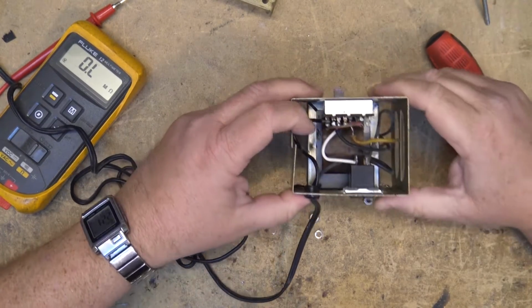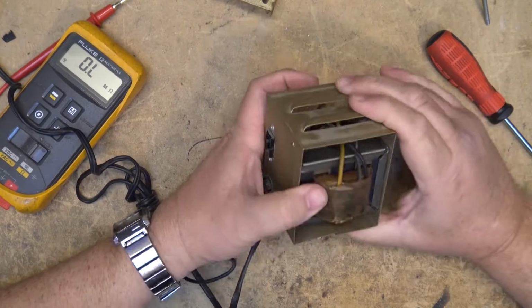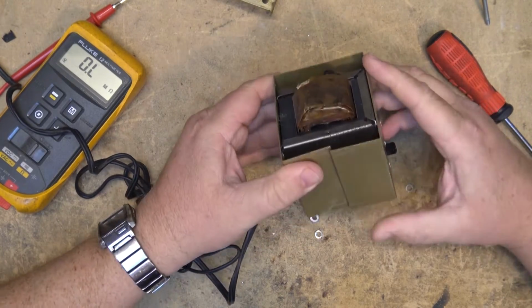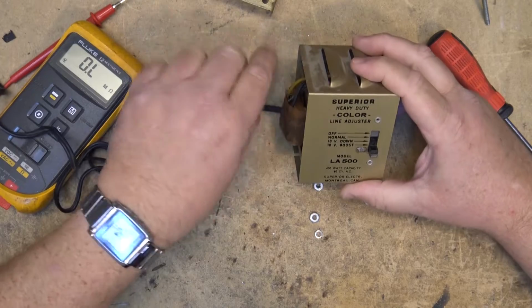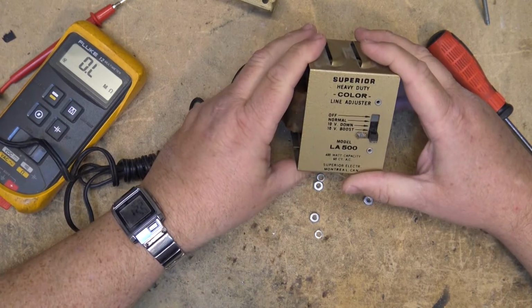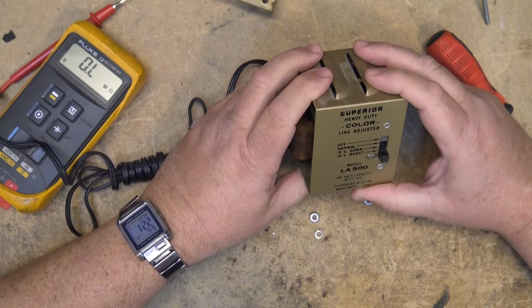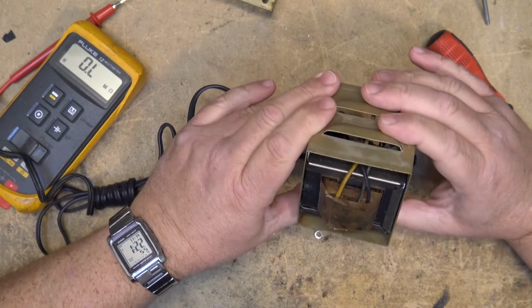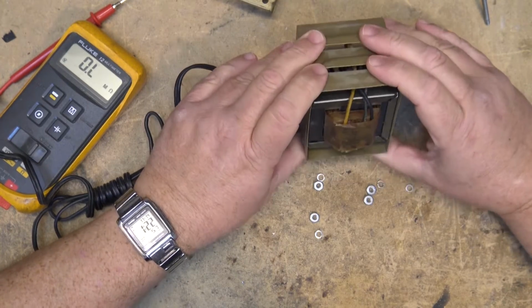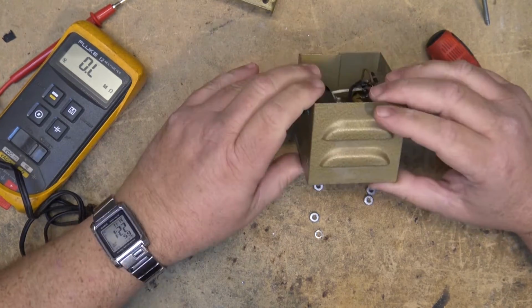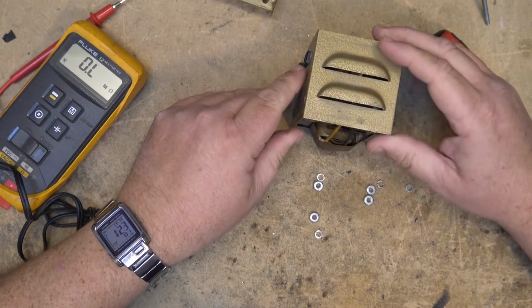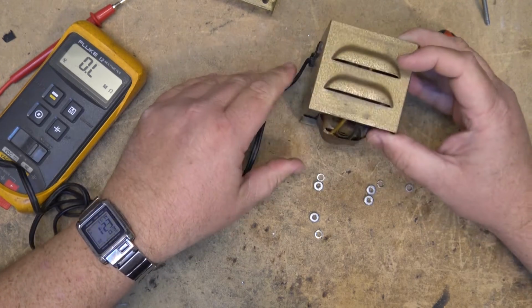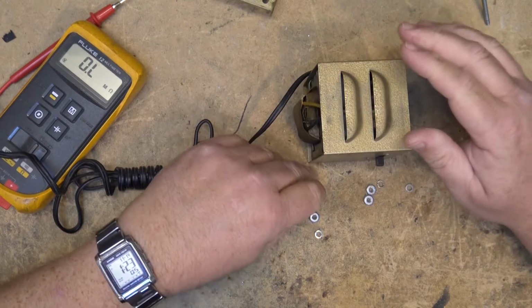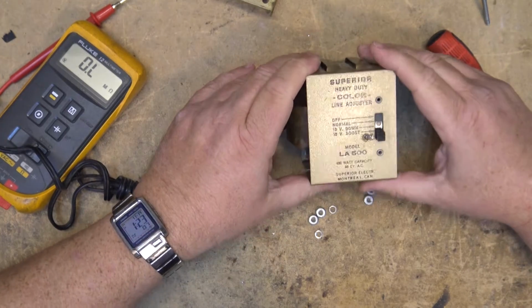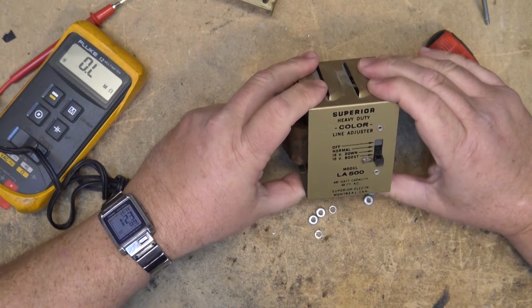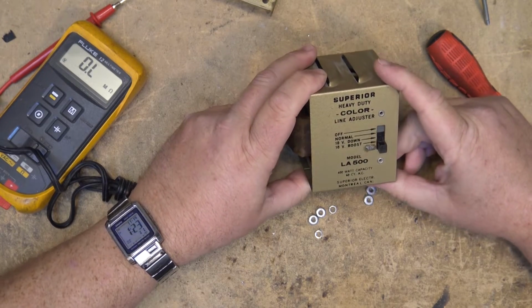So this is not an isolation transformer. If somebody tries to pass one of these things off and tell you that you've got an isolation transformer, it is not, and you are by no means safe servicing with one of these. All this is going to do is boost your voltage up by 10 volts or drop your voltage by 10 volts. These were popular back in the days of tube televisions.